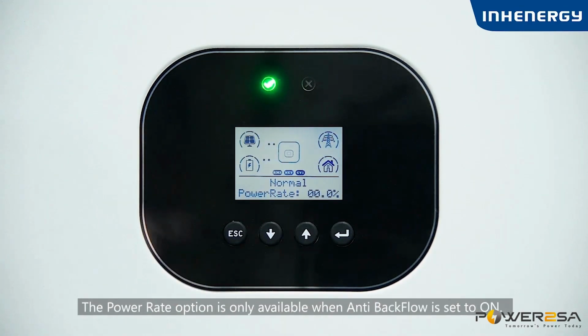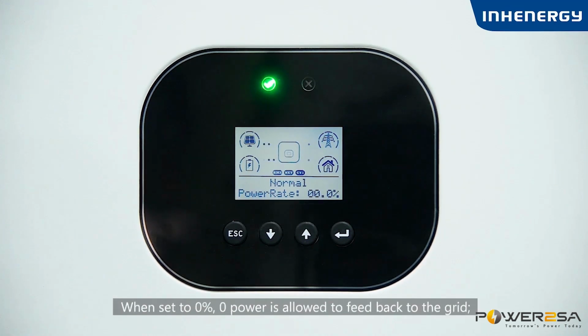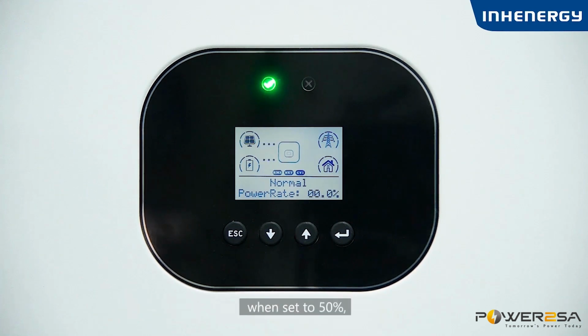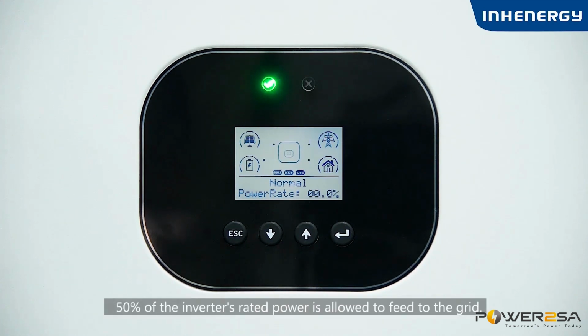The power rate option is only available when anti-backflow is set to on. When set to 0%, zero power is allowed to feed back to the grid. When set to 50%, 50% of the inverter's rated power is allowed to feed to the grid.